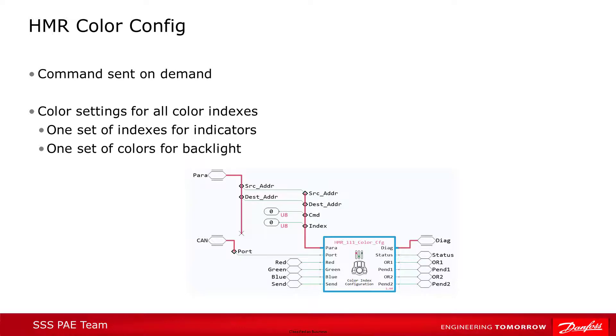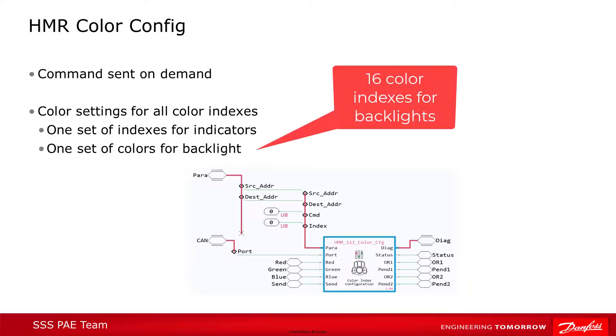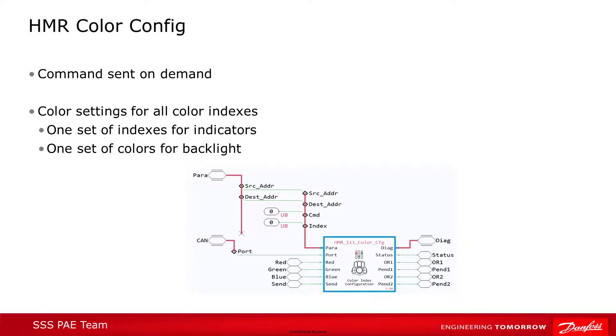The color config block sets the values for the 32 color indexes used by the device. Remember that there are 16 color indexes used for the indicator lights and 16 for the backlight. You can load any RGB value into each color index, which will then be the color displayed by any buttons using that index. There are default colors set for each index, which can be found in the HMR technical information document, but they can be changed to any RGB color. Remember when the index is changed, any buttons LED pointing to that index will also be changed.